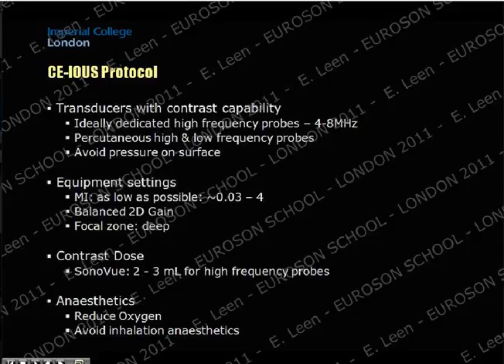Whereas with the intraoperative ultrasound probe with contrast capability, they can go as far down as 0.03 MI. Now, these numbers are very arbitrary, depending on which machine you're working with, so they may not mean a lot. So the answer is go as low as possible on the MI. And if you go as low as possible, you need to be able to counterbalance that with a gain.